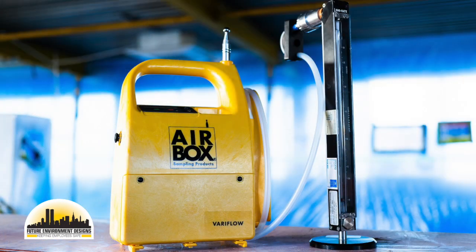I think that's something that as we go out to new markets all the time, you're always getting a slight variation of the same process. And that's what's unique, but sometimes very challenging, in trying to develop a pump that's as much of a one size fits all, while still being robust and doing everything that the pump is required to do. So it was really important for us to make something that was easy to use, easy to carry around. But as you can see, it's fully encapsulated, so IP65 rated.